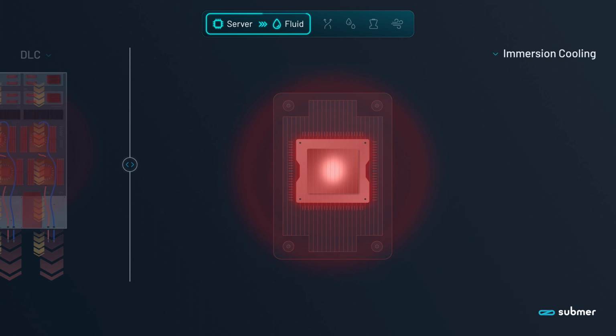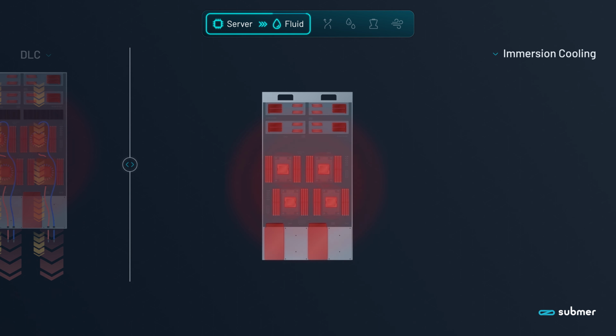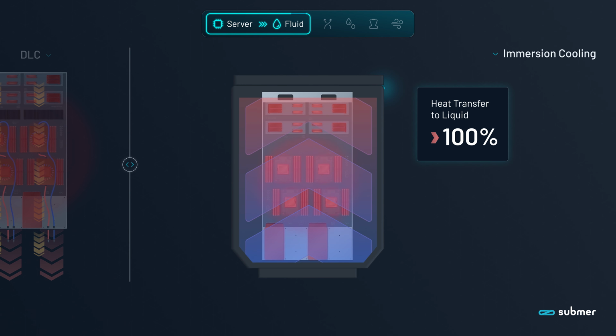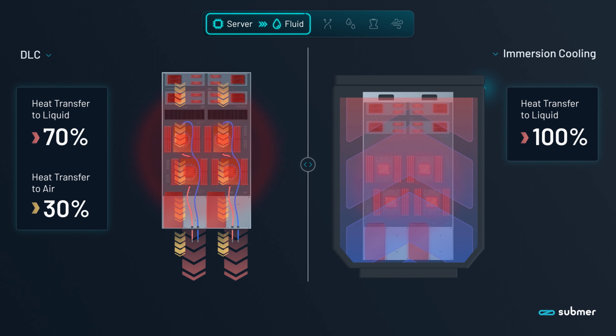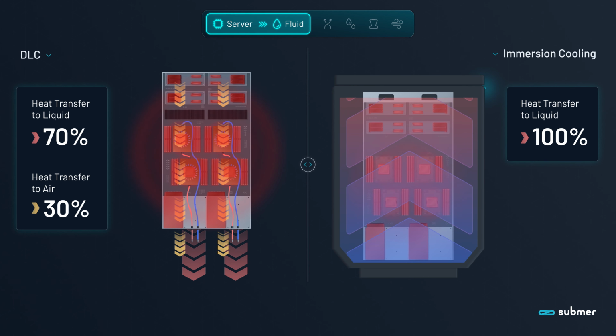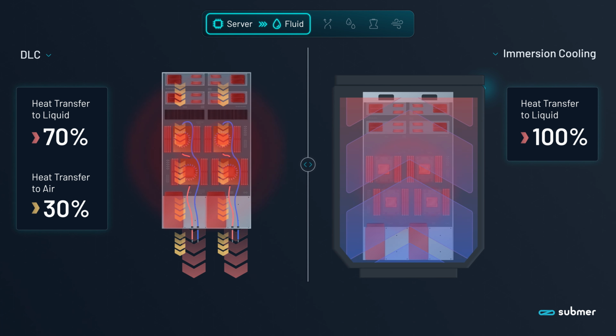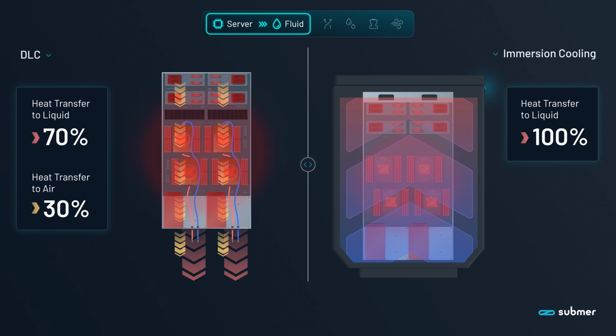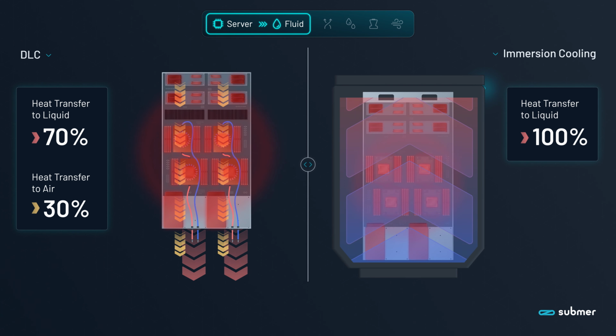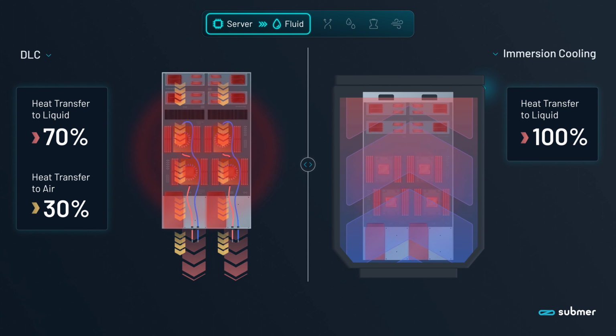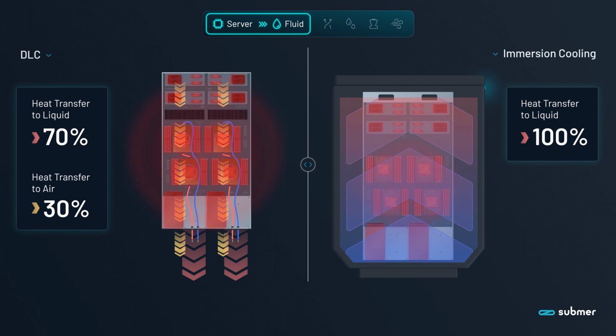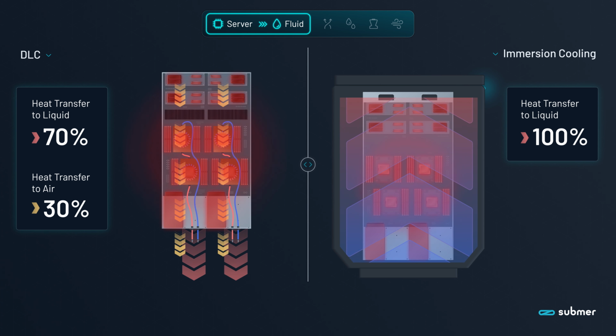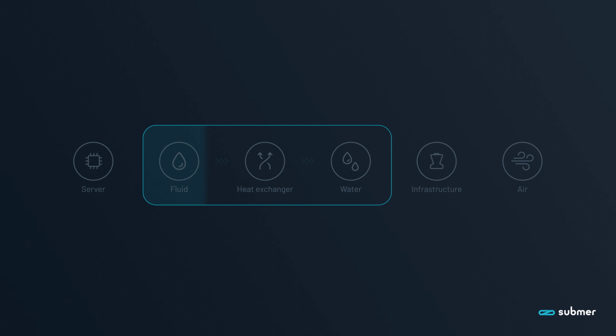In immersion cooling, there is no need for fans. The server is fully submerged in a cooling fluid, which absorbs 100% of the heat generated by all the components. The first heat transfer stage has now been completed, with single-phase immersion cooling showing a clear advantage. It simplifies the server design, with a single body of fluid absorbing all the heat. Now, let's examine the second stage. Here, the heat moves from the primary fluid to a secondary one, usually water.